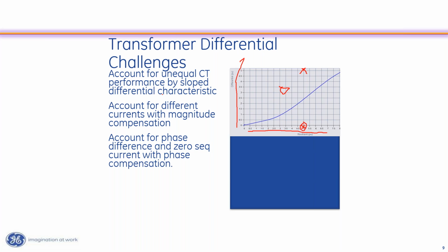So that means, let me find my pen. There's my pen. So that means I've got a differential of 4, because 6 and 10 vectorially sum to 4. And my restraint is the maximum of those two quantities. So that means my restraint would be 10. So I would be somewhere out in here because we're off the graph now. But that's down here in the restraint region, right? So I would not operate. That's how we accommodate this with the slope differential characteristic.